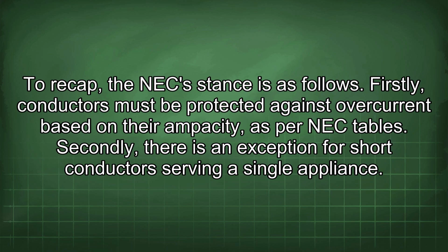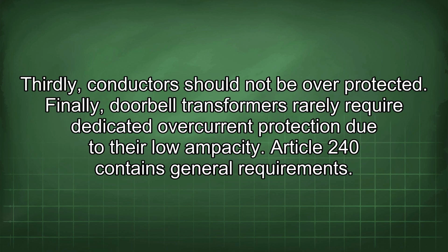To recap, the NEC stance is as follows. Firstly, conductors must be protected against overcurrent based on their ampacity, as per NEC tables. Secondly, there is an exception for short conductors serving a single appliance. Thirdly, conductors should not be overprotected. Finally, doorbell transformers rarely require dedicated overcurrent protection due to their low ampacity.